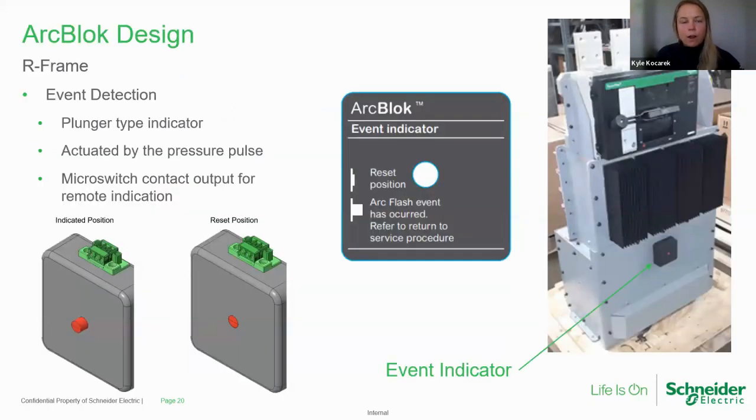So when it has an arcing fault and it self-extinguishes and clears, your breaker doesn't see that. Again, that's all on the line side. It doesn't trip your breaker. It doesn't affect anything downstream. Your operations won't be disrupted. It clears so quickly, there's not even a temperature rise registered. And I'll show a picture.